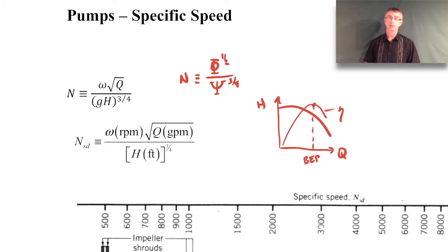And so what happens is these different kinds of pump types, the head rise and flow rate at that best efficiency point is calculated for a particular rotational speed, and then the specific speed is calculated for that. So that's accumulated for many different kinds of pumps. And from those calculations, what you find is you start to see patterns. So you'll find that when you're dealing with high flow rates and low head rises, those axial types of pumps tend to be most efficient under those applications. When you want a lower flow rate and a higher head rise, then the radial style pumps tend to be most efficient for those applications. So you'll find that the best efficiency point changes from high flow rates for axial style pumps to lower flow rates for radial style pumps. And so you start to see this kind of pattern.